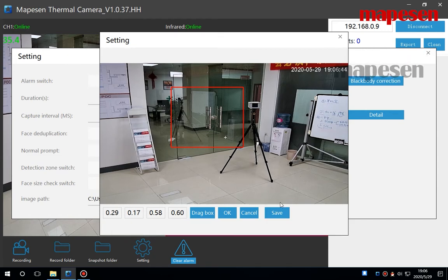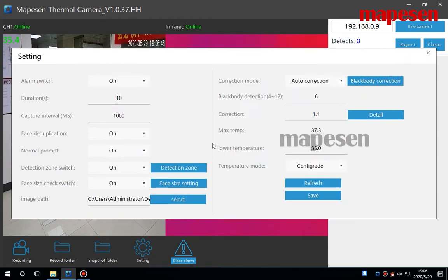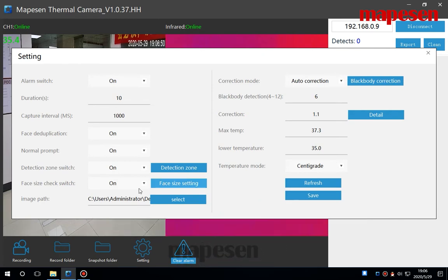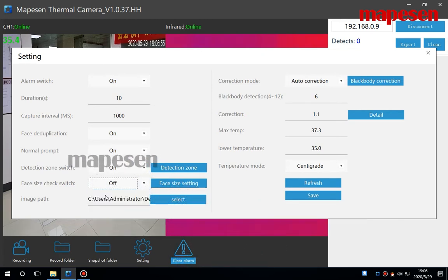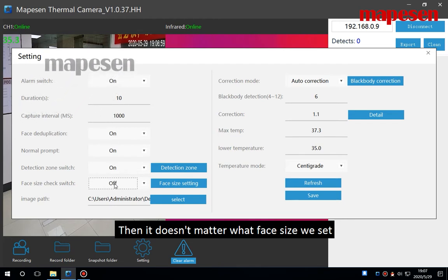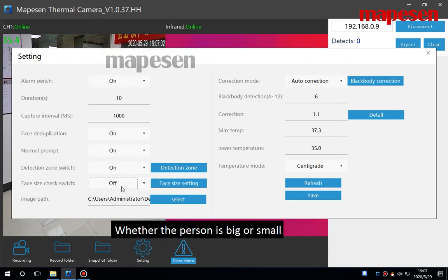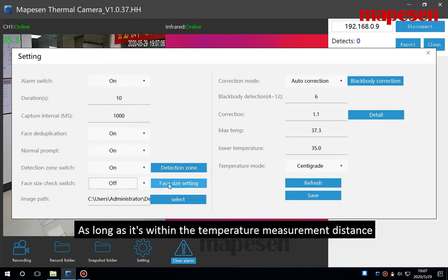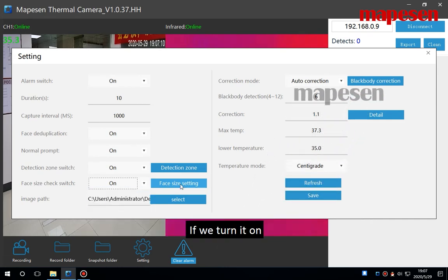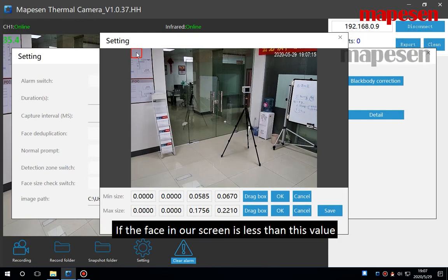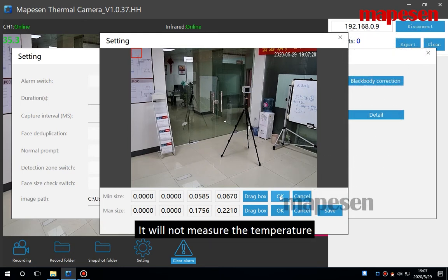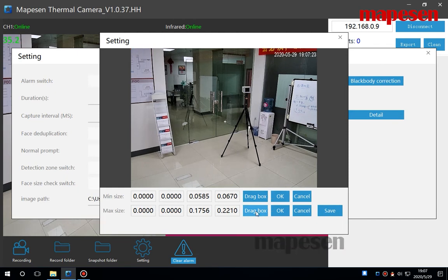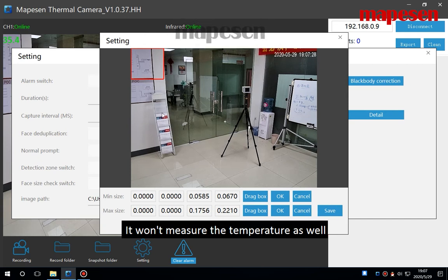That means only the temperature will be measured in this area of the frame. People outside the frame, people outside the area will not be measured. Click save. The next one is the setting for the face size check switch. If it's off, then it doesn't matter what face size we set. Whether the person is big or small, as long as is within the temperature measurement distance, it can measure the temperature. If we turn it on, click this. If the face in our screen is less than this value, it will not measure the temperature. If the face is bigger than the frame, it won't measure the temperature as well.